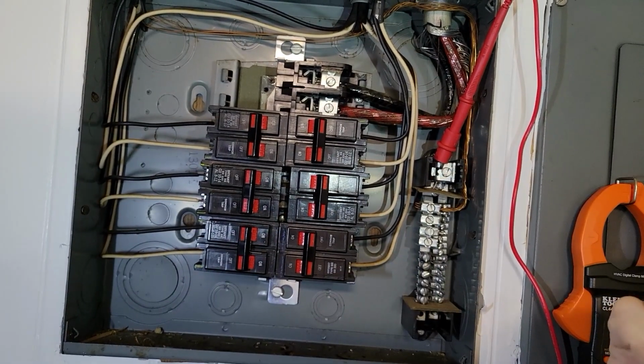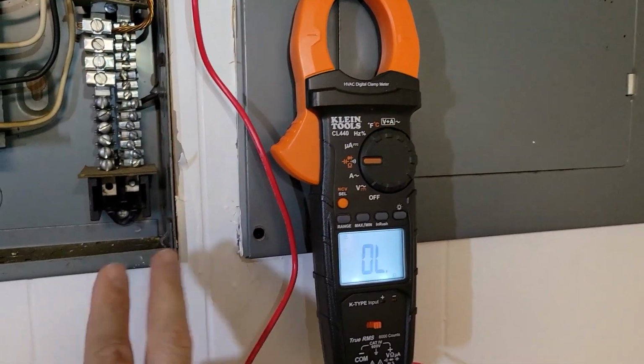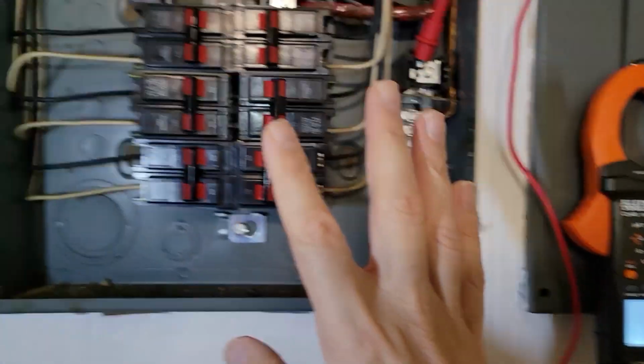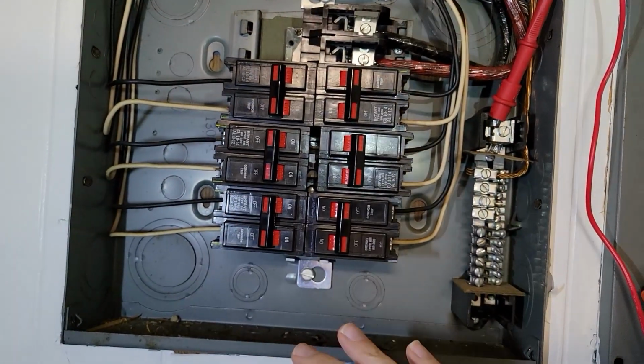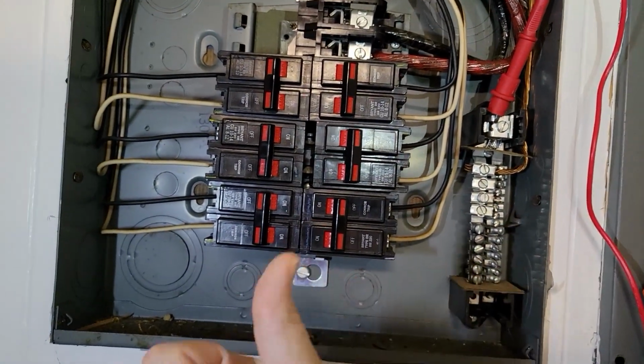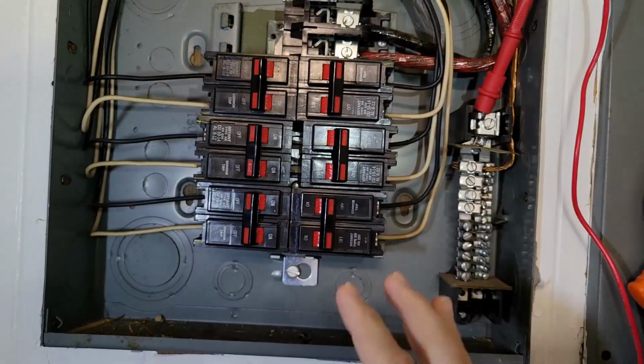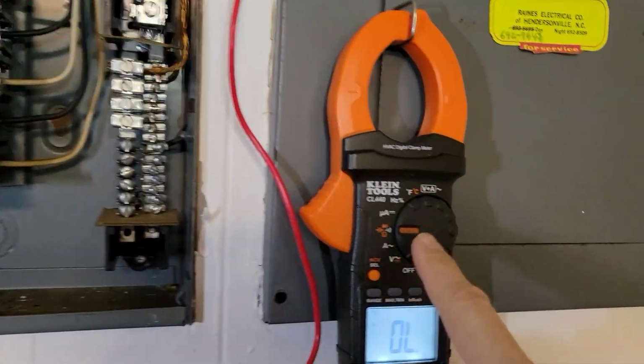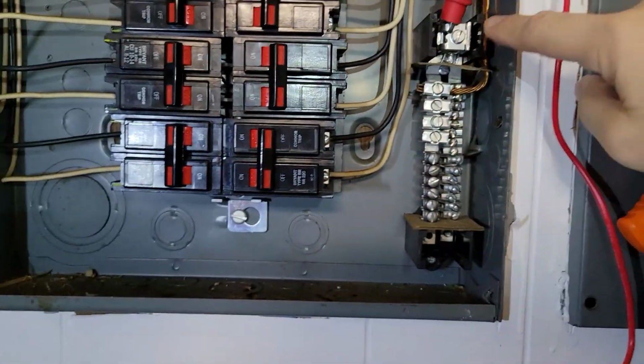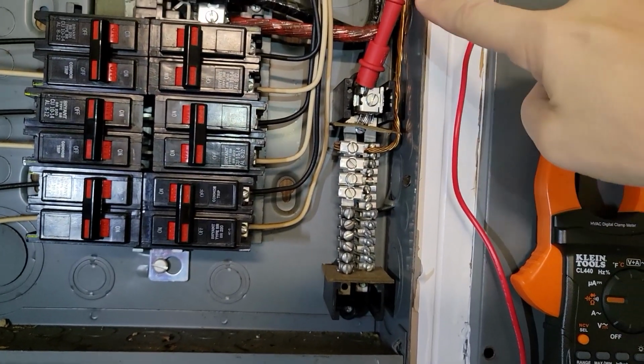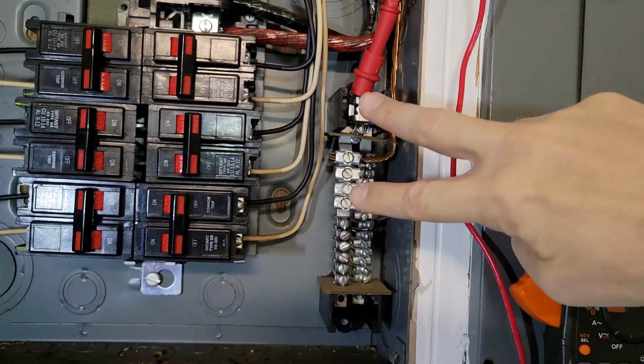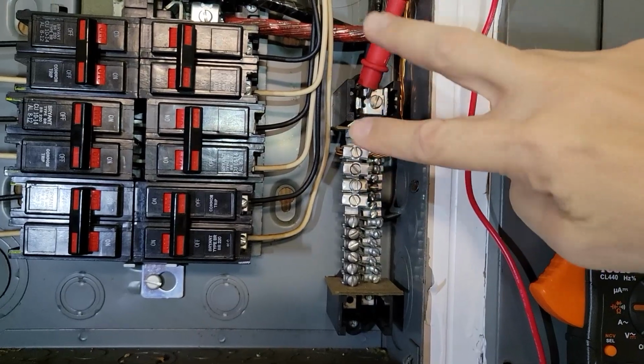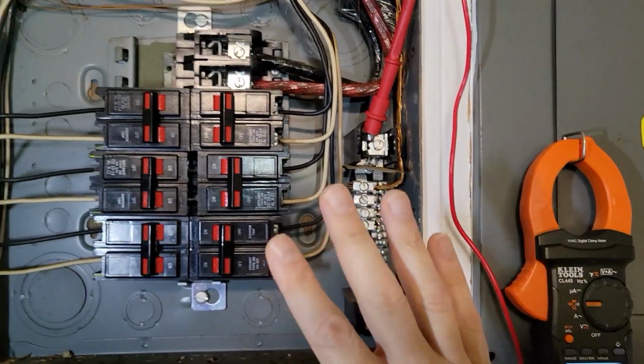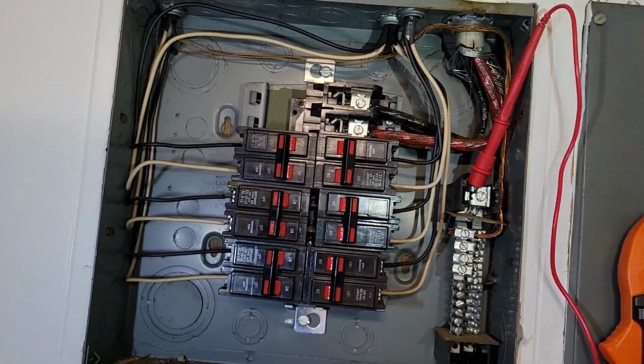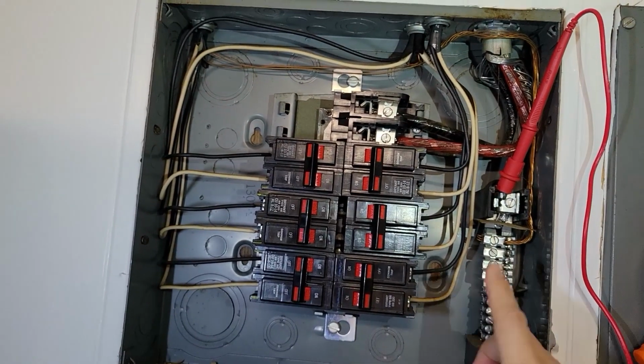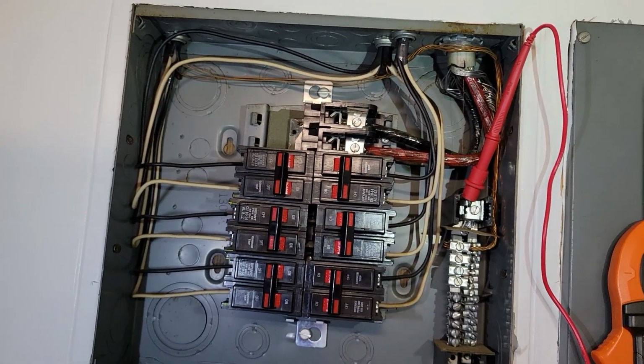It has been tripped off. I've gone through with my meter and verified both that there's no voltage and that there's no back feeding via any other lines. Right now I'm checking continuity, and I've discovered that the neutral bus and the ground bus are bonded, which is a no-no for a sub panel, but was okay back in 1968. So that's an issue I'm going to have to address.